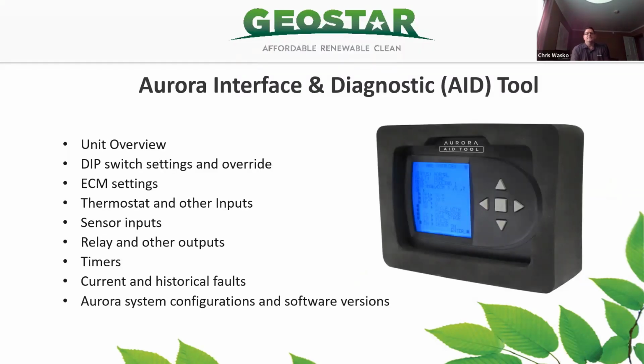The Aurora Interface and Diagnostics tool. This is one of our tools that you can use on any one of our units, whether it's residential or commercial. You have the ability to plug this in either into the control board or an outlet that's supplied to you on the front of the unit. This aid tool allows you to work internally in the unit and look around inside to see what's going on by looking at dip switch settings and being able to even change them, looking at the blower fan, the ECM settings, thermostat and other inputs, sensor inputs, the relays and the other outputs that are going on, the timers in the unit, current historical faults, pretty much unlimited.